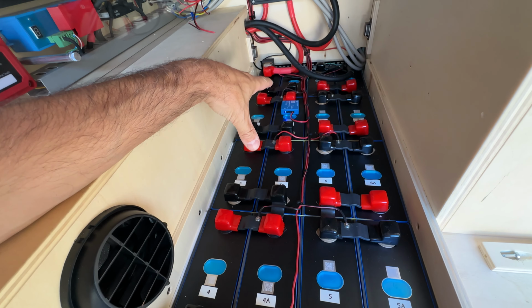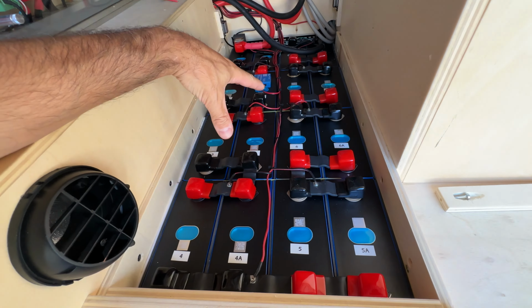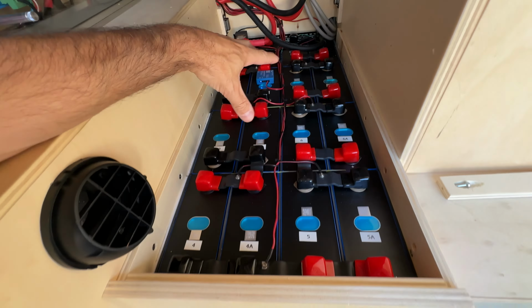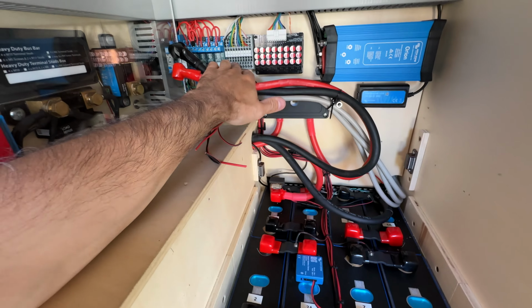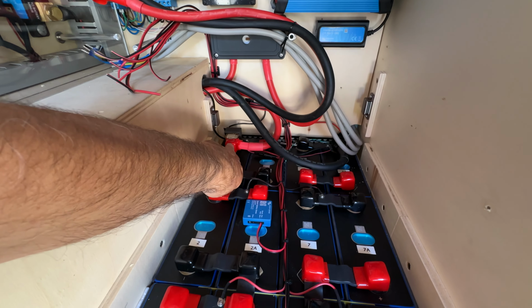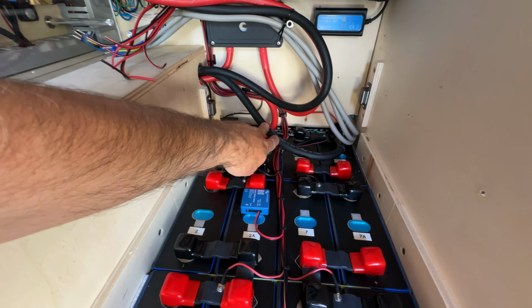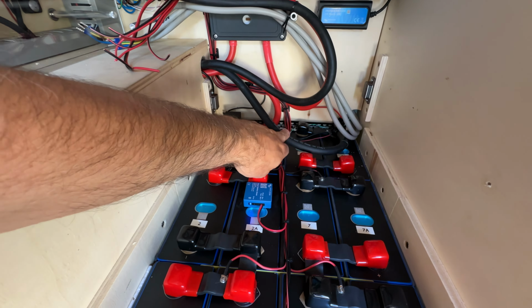The battery is complete. All the bus bars are connected. Still need to tighten the nuts all the way in with my torque wrench. The spec says 8 Newton meters for welded studs like this one has. Still need to connect the BMS balancing wires up here, and I just connected the main positive and main negative loosely, so still need to tighten those as well.